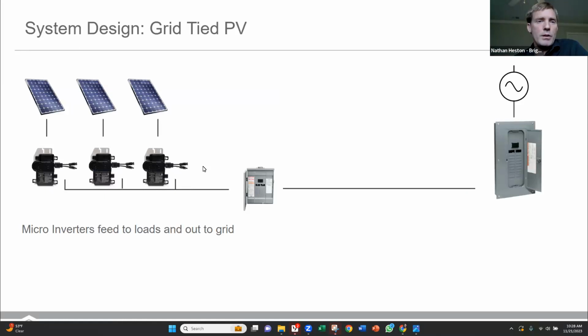So here's an example of an AC coupled system. You've got solar panels. Those microinverters that are shown there on the screen are mounted right on the back side of those solar panels, and 240 volts AC is being fed through two lines back down to a loads panel. That loads panel is then coupled in. There's a shutoff there. Typically, there's a little bit more equipment. There's some communication equipment that goes with those Enphase microinverters. And then you'll be feeding through a fused disconnect. So I'm not showing it on the screen, but you need to have a disconnect for that micro array before bringing it back into the loads panel.